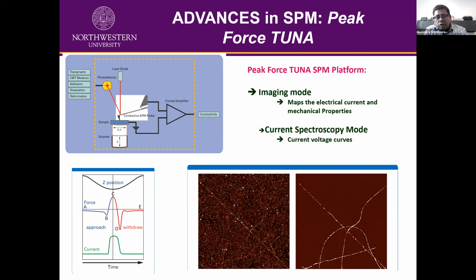Also, given that the cost of these probes is pretty high, they incorporated peak force tapping in this conducting AFM. Now it's called PeakForce TUNA, where obviously the probe applies a pretty low force, so you can sustain a longer lifetime of these probes with the metal coating, and you can get high resolution images.